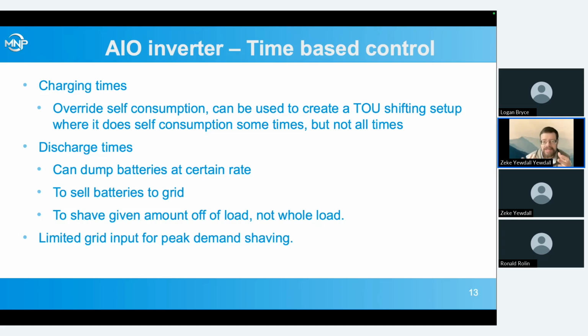These override the self-consumption, and what we most commonly do is say we've got peak rates between 4 p.m. and 8 p.m. What we would do is set it for self-consumption and then set charging times for every time except 4 to 8 p.m. So that overrides the self-consumption and charges the batteries during those times. During 4 to 8 p.m., there's no charging time set. It goes into self-consumption. It discharges the batteries till we get to 8 p.m. or until we hit our minimum reserve SOC on grid.